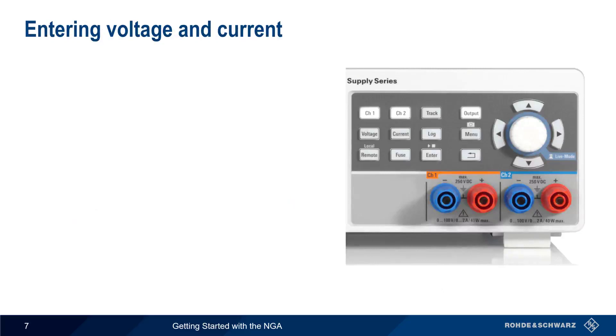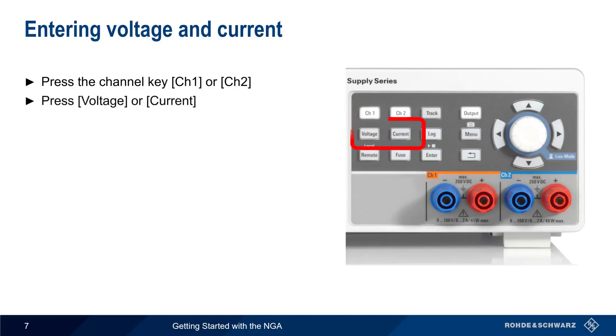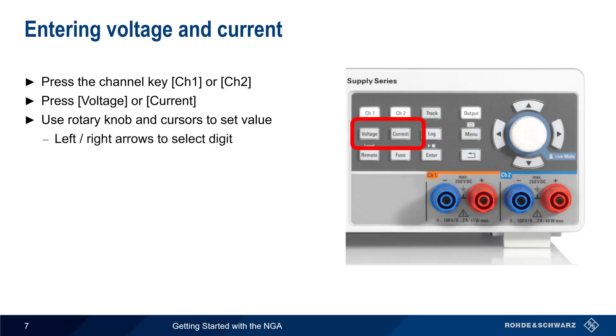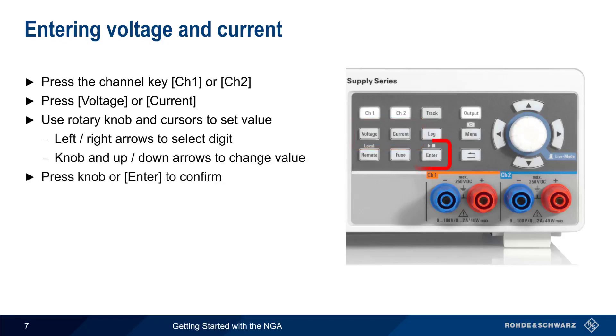Once connections are made, we enter values for voltage and/or current, and then enable output. For two-channel models, you'll need to select channel 1 or channel 2 using the hard keys, and then choose either voltage or current. Values are set using the rotary knob and cursor keys. Use the left and right arrows to select the digit, and either the knob or the up and down cursor keys to change the values. Confirm values by pressing the knob or the enter key.